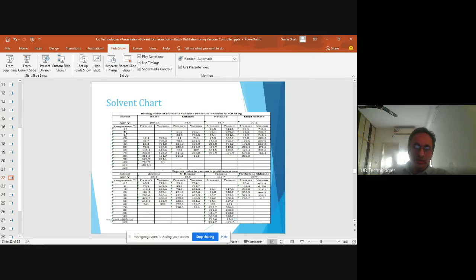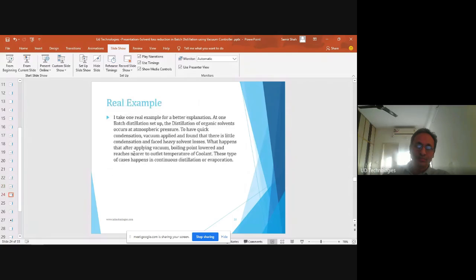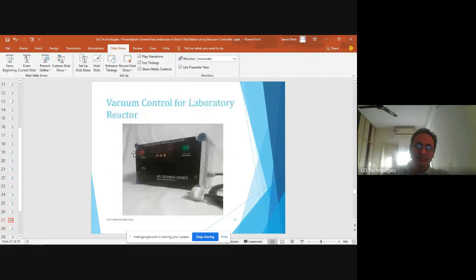It will increase the absolute pressure or decrease the vacuum. So your boiling point will increase. So the cooling tower, cooling water and chill water will condense the ethyl acetate more efficiently, right? So this is the funda of the vacuum control. So if you use the higher vacuum, or sorry, higher absolute pressure, then the condensation will be better, right?